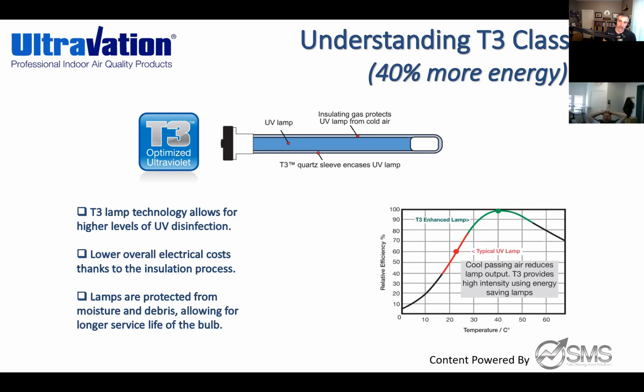The clarification here is a standard UVC wavelength bulb is actually only a 9,000 hour life bulb, meaning from a PM standpoint, you guys should be changing the bulbs annually. Once that bulb has been lit up 24/7 in an HVAC system, there's a life cycle — it's burning through, emitting that UVC wavelength constantly. So at the end of the year, with a 9,000 hour life cycle, you've probably burned through, depending on the environment, anywhere from 40 to 60% of its potency. That's why they want you to change it annually.